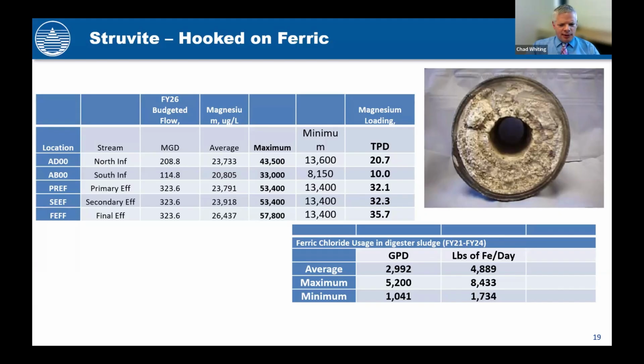So we tried acid washing to remove the struvite with hydrochloric acid. We had glass lined piping, and we thought we'd be okay acid washing the piping. After a couple of acid washes, we started seeing pinholes in the piping and started developing leakage. Glass lined ductile iron piping is not perfectly lined. There are imperfections in that lining that the acid was able to find its way through to the piping and cause damage to the outside of the pipe. This resulted in about $5 million in replacements for the overflow line system due to that acid washing of the piping.